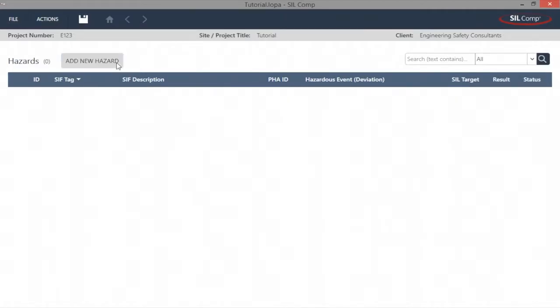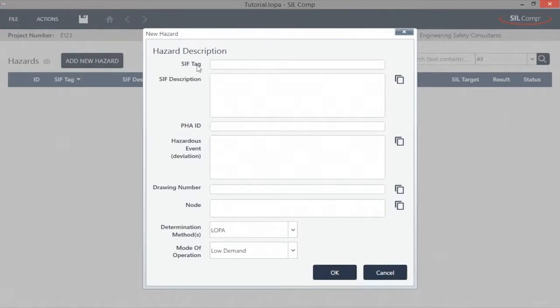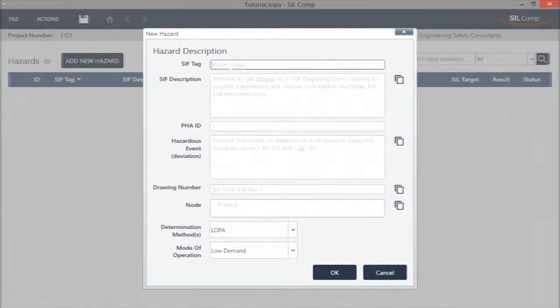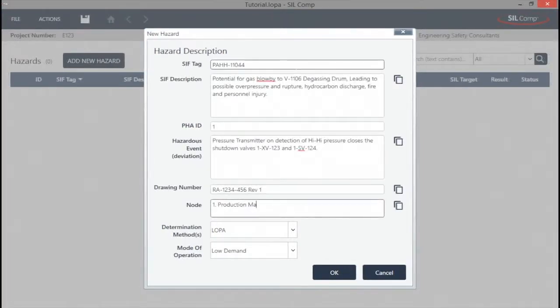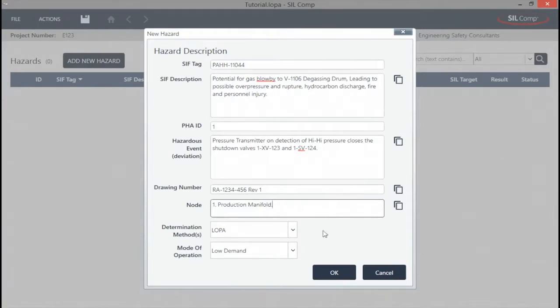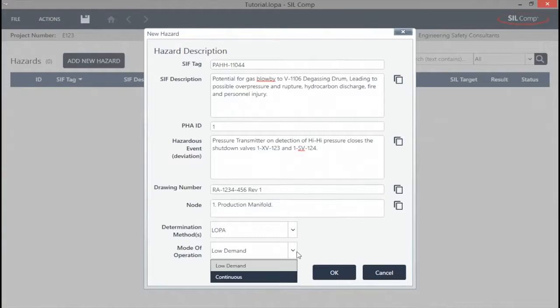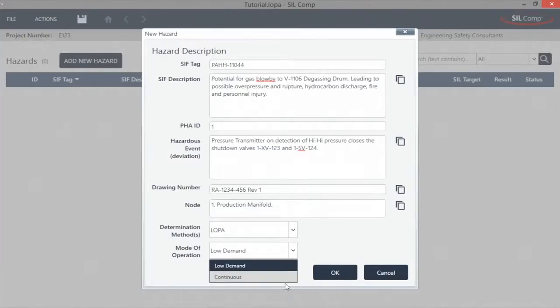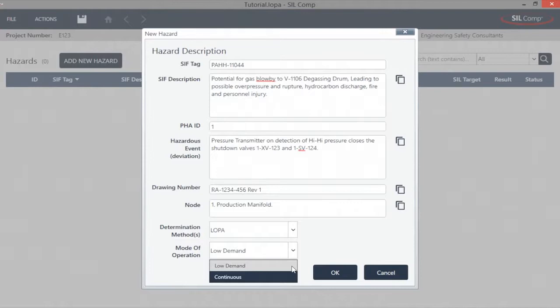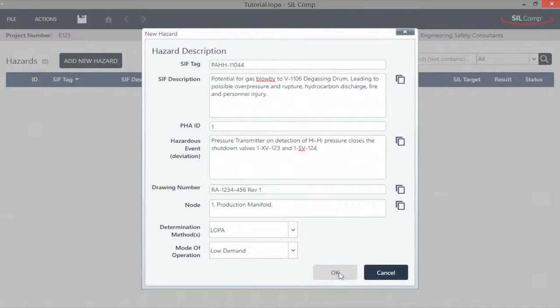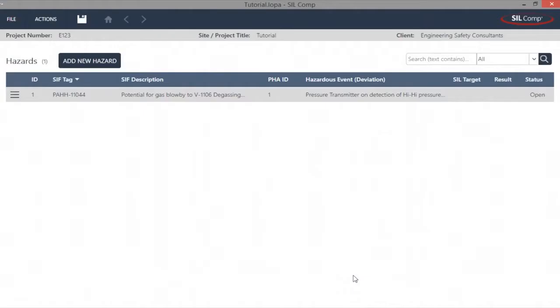Adding a new hazardous event couldn't be simpler. SILCOMP allows you to record all the vital information that is required and facilitates full traceability from the drawing number and node being analyzed. The module allows for differentiation between low demand mode of operation, where the target failure measure is the PFD average, and high demand or continuous mode of operation, where the target failure measure is the PFH, that is, the probability of failure per hour within one hour.